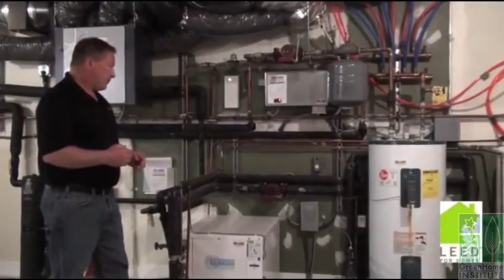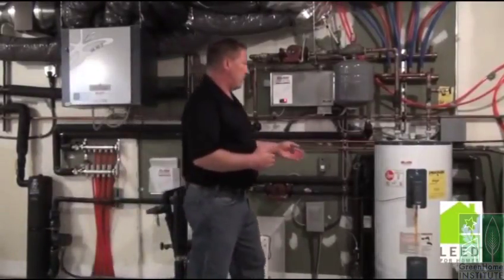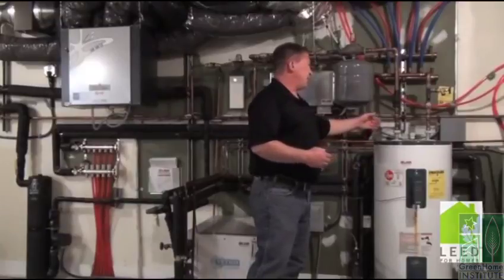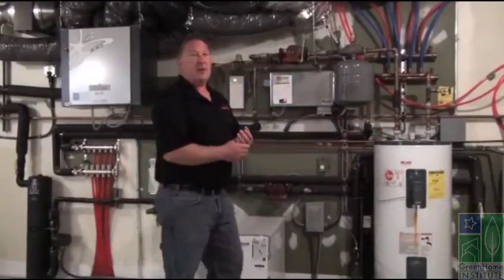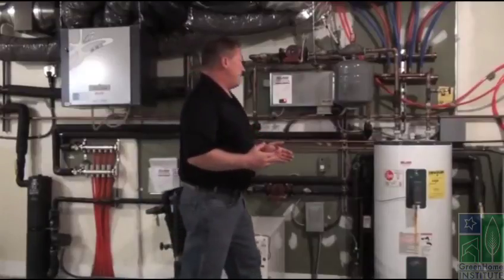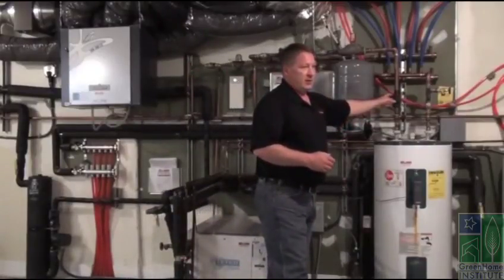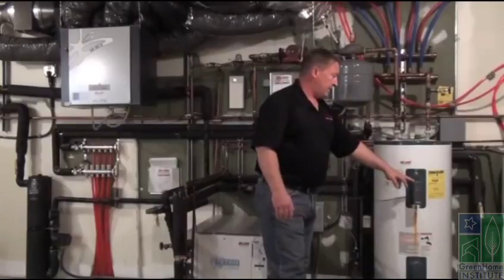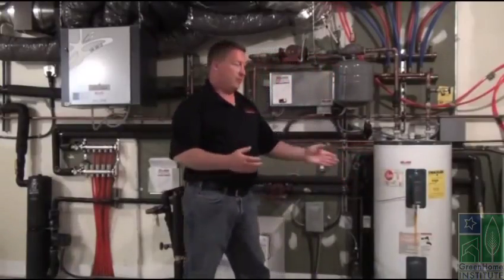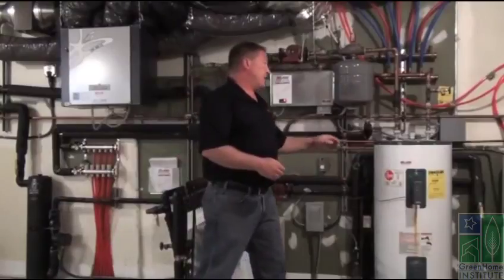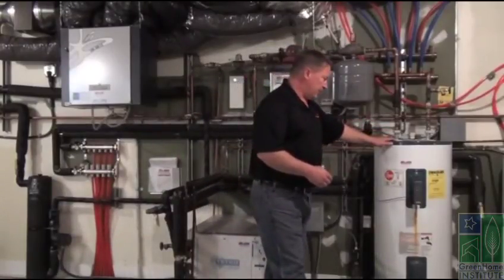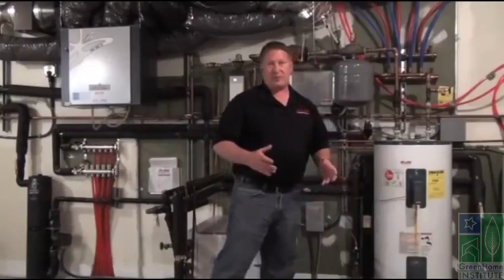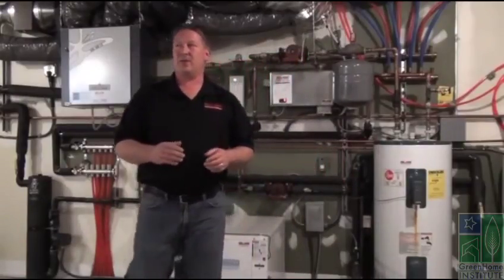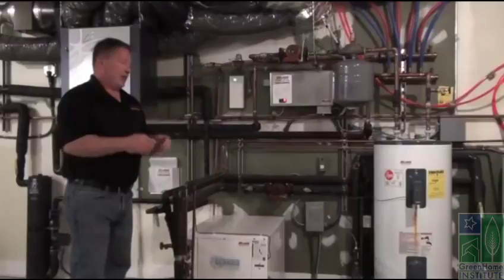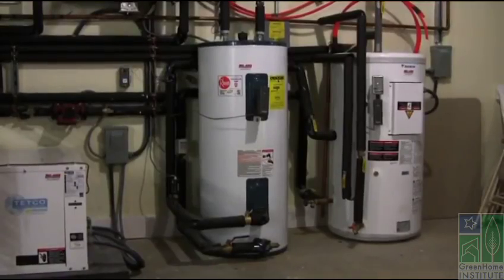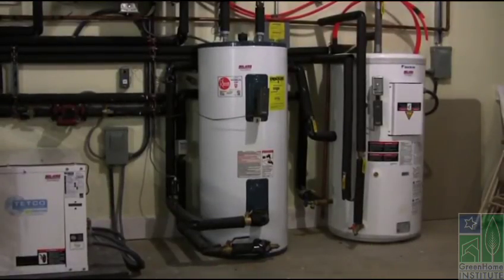Again, the house is still cooling, the water is still cold enough to remove heat from the house. And then as the load increases, the water temperature will increase, and this thermostat then will allow the geothermal to come back on. So kind of two different concepts. We have this thermostat in cooling mode is like a low limit. This thermostat in heating mode is actually the thermostat that controls the temperature of the tank. So summertime, we're running about 55 degree water through the system. Wintertime, we're running 110, 115, 120 degree water. And that tank's going to maintain that at all times so that we have a buffer, we have enough capacity when we ask for it.